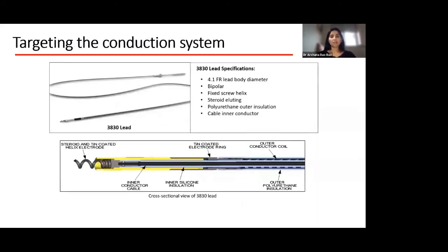How do we target the conduction system? Well, the industry have been partners in this. We have a selected lead called the S3830 lead, or the Select Secure, which is a cable design lead with a 4.1 French diameter, which is catheter delivered to the area of interest, i.e. the conduction system, where it has a deployable screw, a helix, that is deployed into the conduction system. It has a polyurethane insulation and reasonably good extraction data for the future.